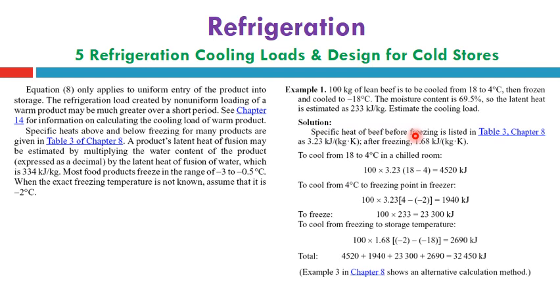Specific heat of beef before freezing is listed in table 3, chapter 8, equal to Cp = 3.23 kilojoule per kilogram Kelvin, and after freezing 1.68 kilojoule per kilogram Kelvin. To cool from 18 to 4 degrees Celsius in a chilled room, we multiply 100 kilogram by the Cp above freezing, multiplying by the initial temperature minus the temperature at which it will start to freeze. So we can get 4520 kilojoule in the first term, which is listed in the previous slide as Q2.